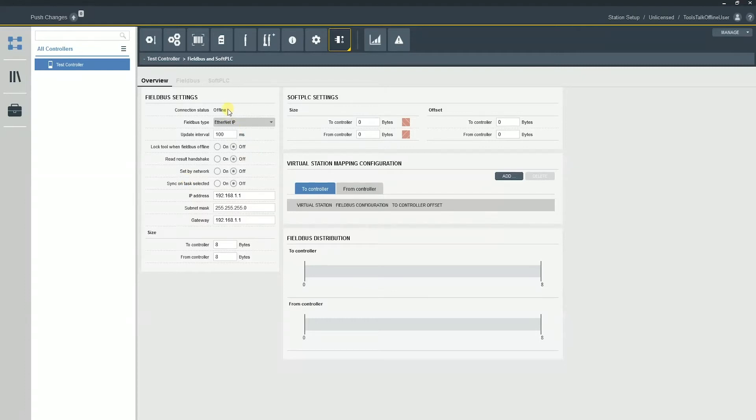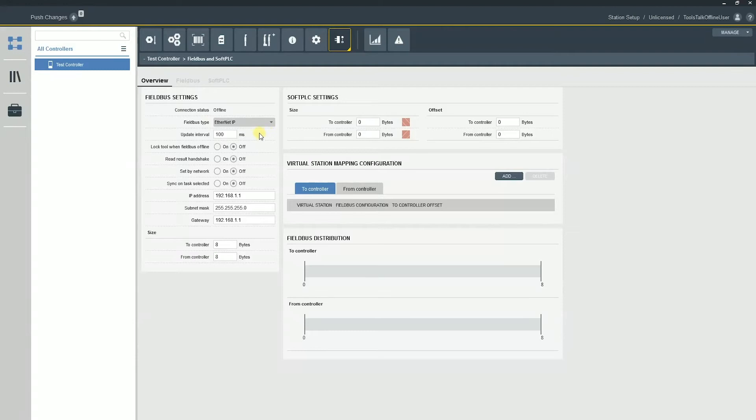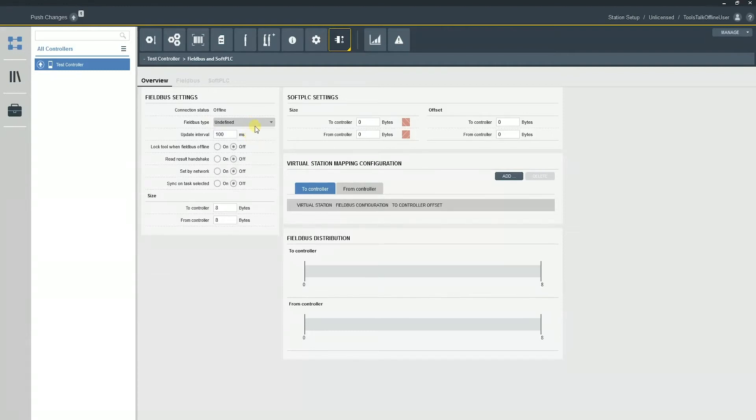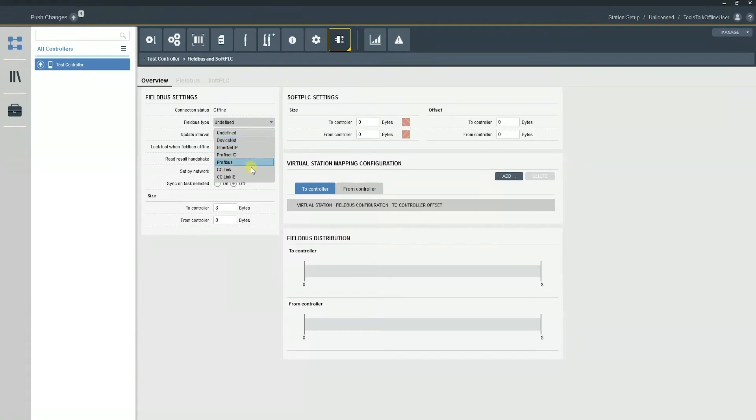So this is going to be our active connection status with the PLC. So until that says online, they're not going to show a good connection to the controller. So that's going to be actively updating right now. I'm not connected to a PLC, which is why it shows offline. The fieldbus type, this is going to be selected. If it's undefined, it's just because we're messing around training or something like that. But we have our six options that are supported with the power focus 6000.